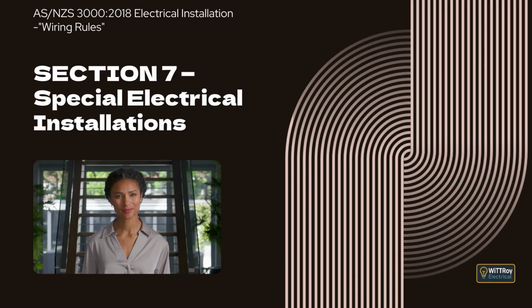Clause 7.1.2 Selection and Installation. This clause explains that each type of special electrical installation has its own specific requirements, and these requirements can replace or change the general rules found in other sections of the standard. It also makes clear that if Section 7 does not state a specific requirement for a situation, then the normal requirements from the other sections of ASNZS 3000 still apply.